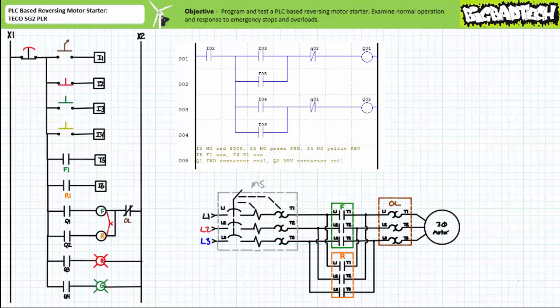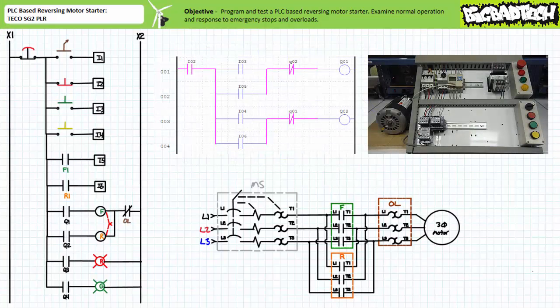Note that neither the e-stop, the overload, nor the mechanically interlocked contactors make an appearance in this program; however, these devices are readily apparent in the hard-wired schematic. Wired in this fashion, the e-stop and overload serve to override the PLC program in the event of an emergency stop or overload event, and the mechanically interlocked contactors prevent simultaneous closure of the forward and reversing contactors. When the program is downloaded to the target device and placed into operation, we can observe its behavior and simultaneously monitor the program using a live communications link — though there is a noticeable lag in the monitoring utility.